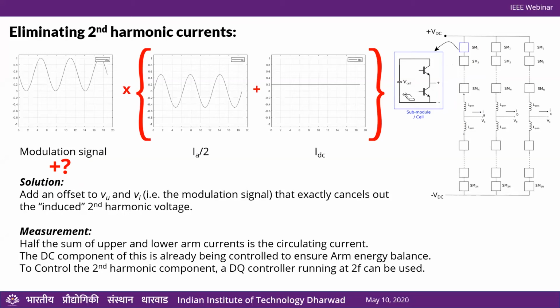So how do we find out? First, you take the arm current and find its average value. That gives you the DC component flowing here, because the differential component just flows out on the phase. That average component—we've already figured out the DC component was being controlled to do arm energy balance, so that's already being handled.